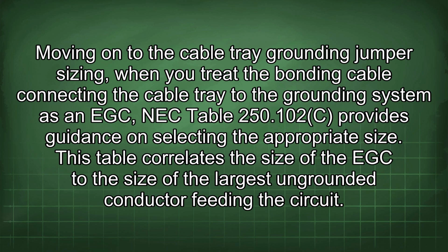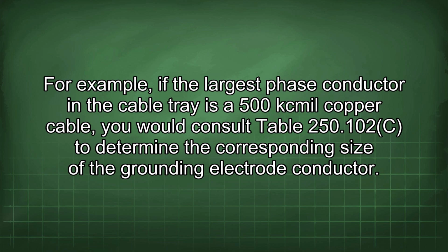Moving on to the cable tray grounding jumper sizing, when you treat the bonding cable connecting the cable tray to the grounding system as an EGC, NEC Table 250.102(C) provides guidance on selecting the appropriate size. This table correlates the size of the EGC to the size of the largest ungrounded conductor feeding the circuit. For example, if the largest phase conductor in the cable tray is a 500 kcmil copper cable, you would consult Table 250.102(C) to determine the corresponding size of the grounding conductor.